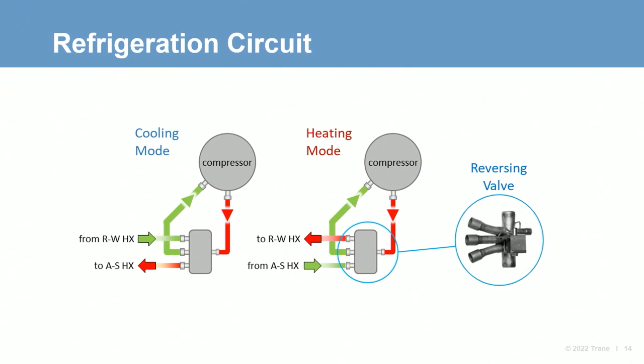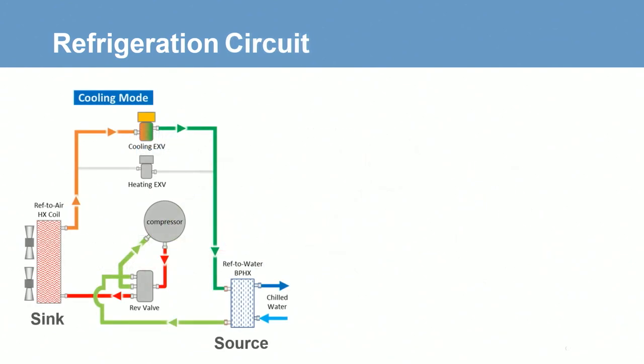Let's start by focusing in on the refrigeration circuit that makes a heat pump unique. The refrigeration component that enables changeover between the cooling and heating is a refrigerant reversing valve, or a four-way valve. A reversing valve switches the flow of refrigerant through the heat exchangers depending on unit mode of operation. The refrigerant always flows through the compressor in the same direction. The reversing valve coordinates flow direction through the refrigerant to water and the air source heat exchangers in the unit. When the unit needs to provide cooling to the building, the refrigerant to water coil is the energy source for the refrigeration circuit, absorbing heat from the chilled water. The refrigerant to air coil is the energy sink by rejecting heat to the ambient air. In this mode, the unit has the exact same operation as an air-cooled chiller.